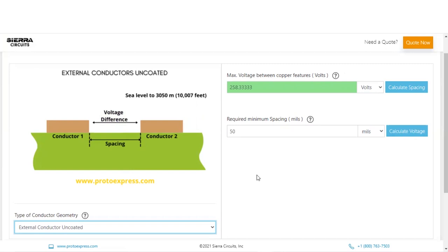This calculator now automatically displays a new maximum voltage. For the same 50 mils spacing, the maximum voltage allowed for an external uncoated conductor is 258.33 volts.